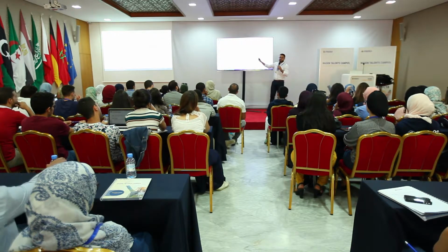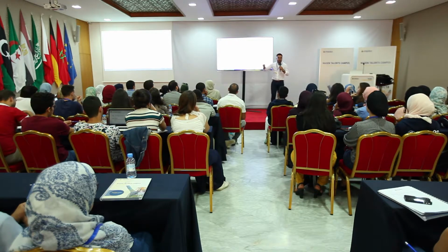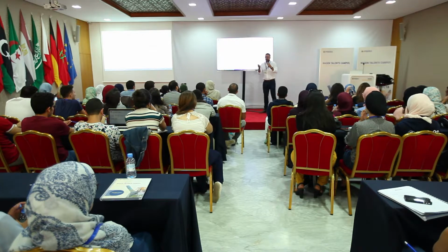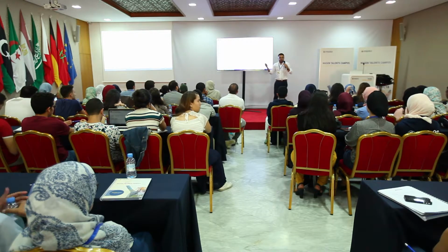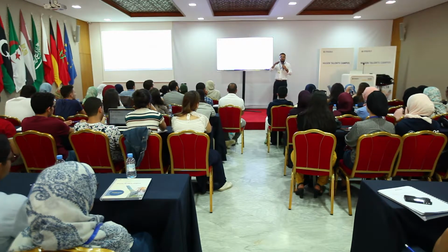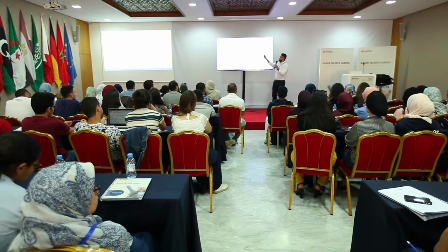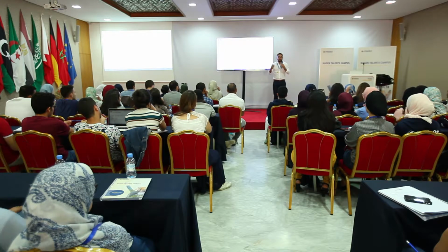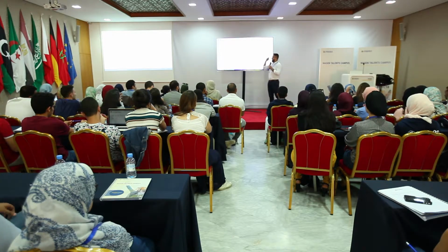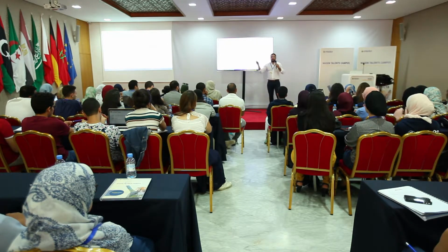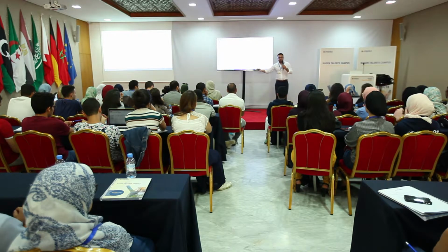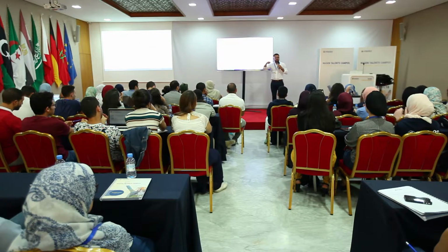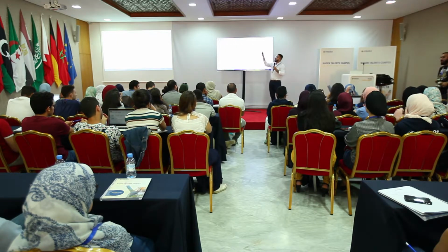Once you have the output, let's say the yield, like what I talked about before here, the yield can be calculated already here, at the annual performance. Then you can calculate the other indicators that I mentioned before, like the LCOE, because you have the yield, you have the cost. So you can calculate the profits, you can calculate all this stuff. If you start varying the size of the components, repeating this process iteratively, you're going to end up with a power plant that will meet your objective, minimizing LCOE, maximizing whatever your objective was.